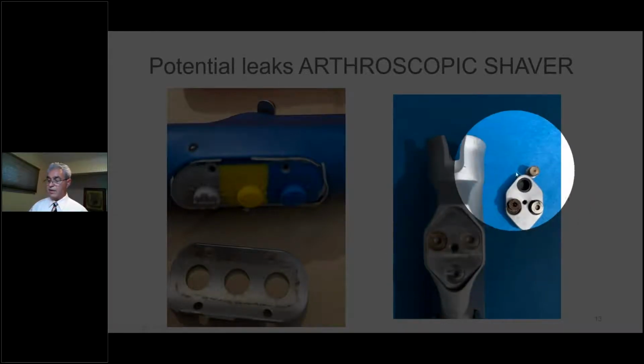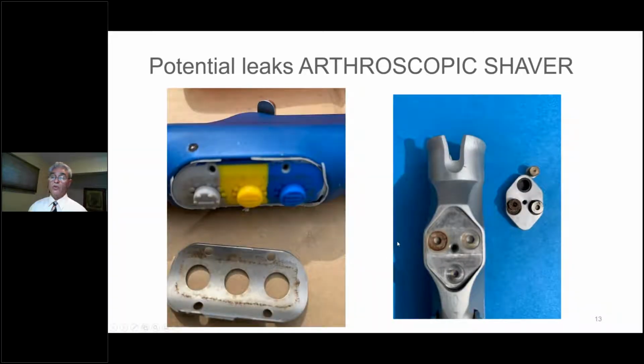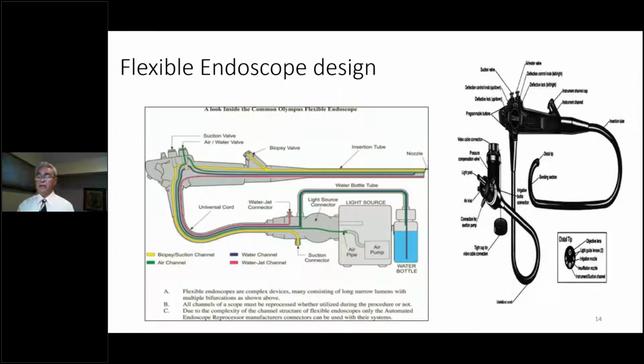So here's an O-ring where something happened, and there's obviously fluid invasion here, and you see that it rusted. If rust gets onto an electrical component, it would get damaged. I'm sure one quick way of knowing is that the handle gets really hot, because you're creating a lot of resistance inside that handpiece, and it could even cause a burn or injury to the user and the patient.